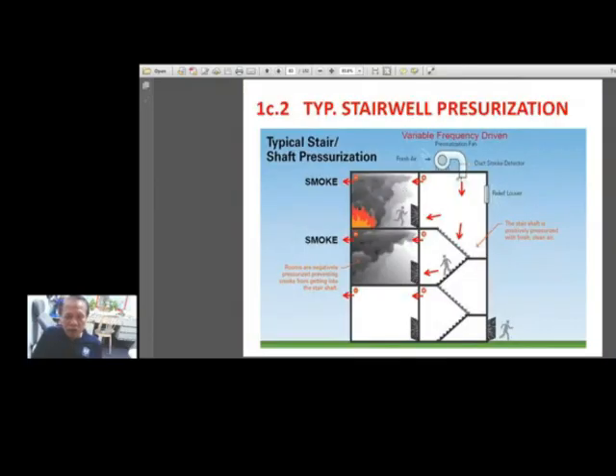And of course, today, with the technology of inverter control, this motor now uses a variable frequency drive. Okay, no longer using the across the line or full voltage motor run or the Y delta run. No more. You have to use this variable frequency controller.